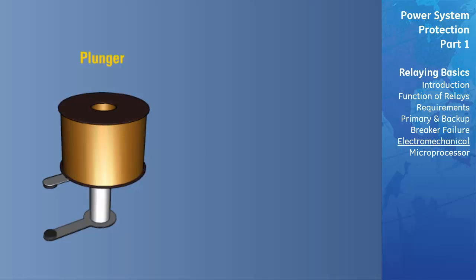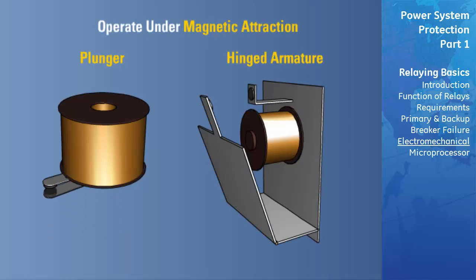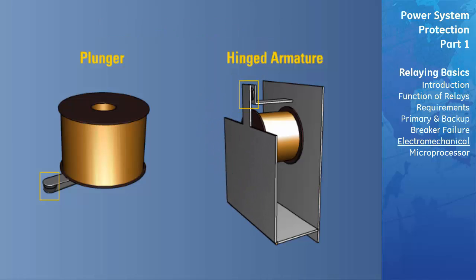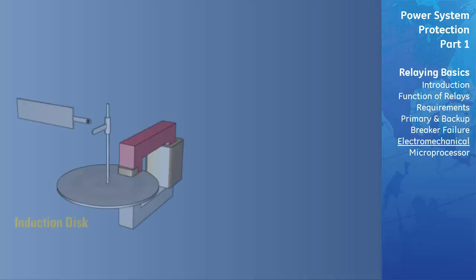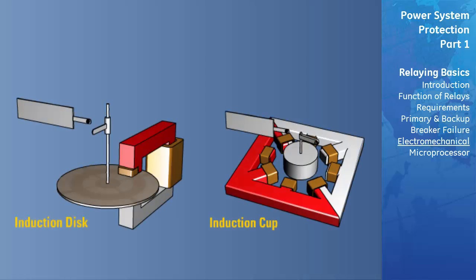The plunger and hinged armature operate under the principle of magnetic attraction. The armature is attracted into a coil or to the pole face of an electromagnet. This principle works with either alternating or direct current measured quantities. The induction disc and induction cup work under the principle of magnetic induction. Torque is developed in a movable rotor in the same way that it is produced in an induction motor, which means that they can only be used with alternating current measured quantities.